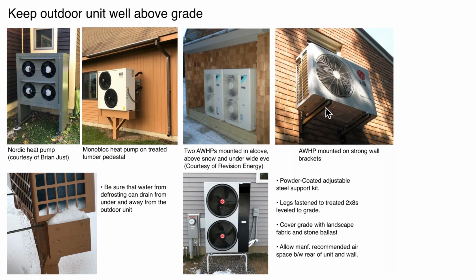Obviously, you want to make sure that that bracket system, if you're going to do this, is rated to hold the weight of whatever unit you're going to put on it. Here's another common approach. This is an adjustable steel stand where you can adjust the height of those legs. It is important, again, in my opinion, what you don't see here under this crushed stone, there's two pressure treated 2x8s, and that stand is fastened down to them, and they're actually down in the ground 3 or 4 inches. It's important to make sure these units are fastened down. If you get a strong wind, and I don't mean an everyday breeze, but imagine a 40 or 50 mile per hour gusty wind, these units can rock around. So you want to make sure that you've got that secured against any kind of wind buffeting.